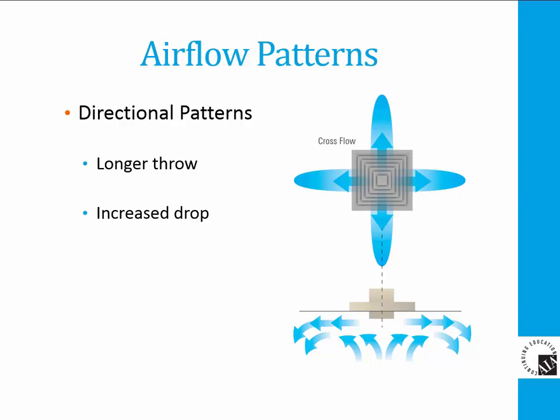The second type of pattern is a cross flow pattern, sometimes called a directional flow pattern. With a cross flow or directional flow air pattern, air is discharged with longer throw in individual sides of the diffuser. The illustration shows a four-way discharge, but it could be three-way, two-way, or one-way as well. With less room air induced into the air pattern, the jet travels a longer distance to a given terminal velocity.